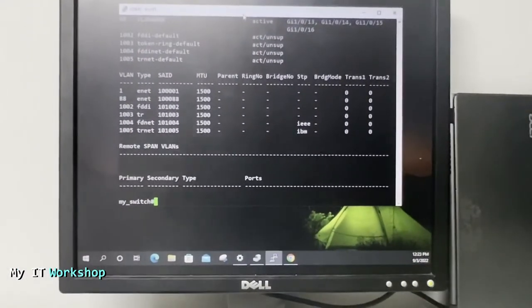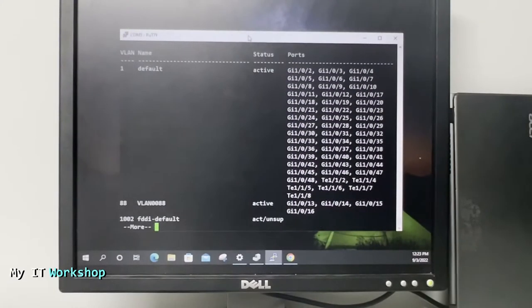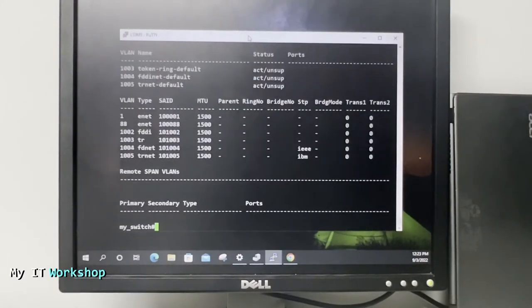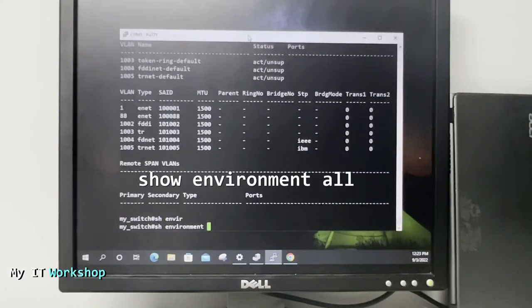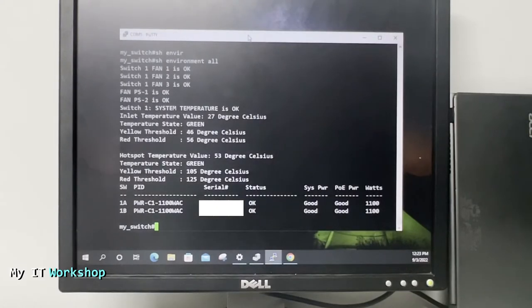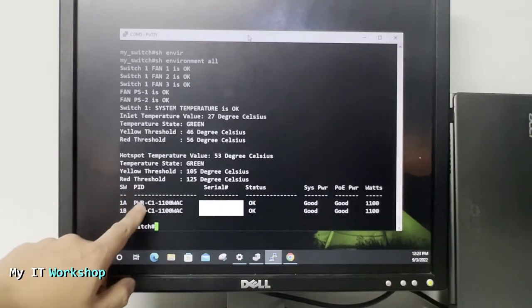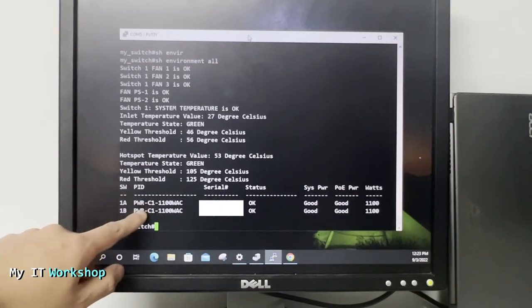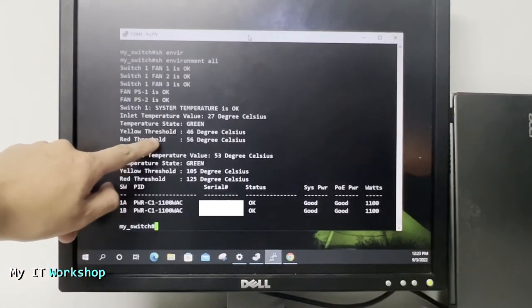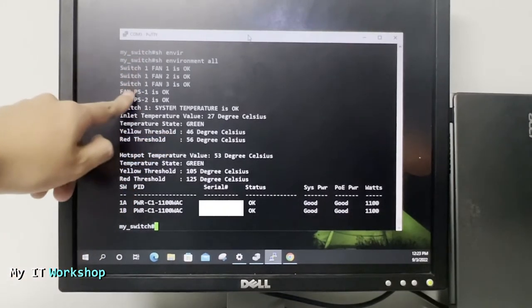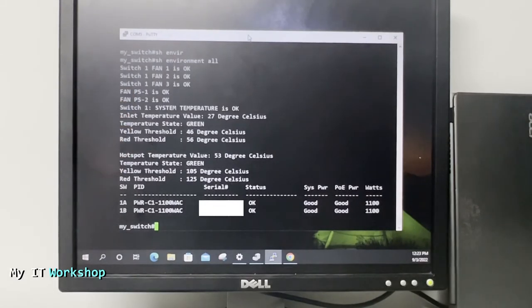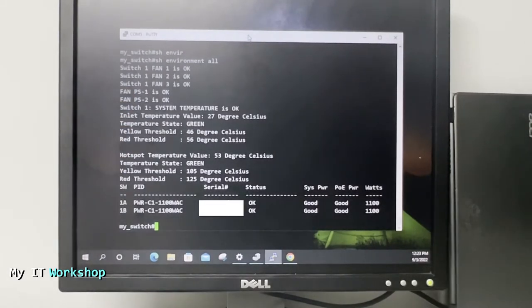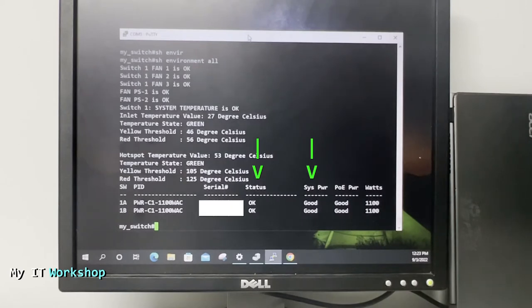The switch is on and I'm using PuTTY for the command line. I'll type the command 'show vlan' just to show you it's returning information. Now I'll type the command 'show environment all'. This command gives you a lot of information about the power supplies. As you can see I have two power supplies, A and B. Above we see the temperature at which they're working and the status of the fans. The status of the power supplies shows they are okay, system power is good, power over Ethernet is good, and how many watts they consume.